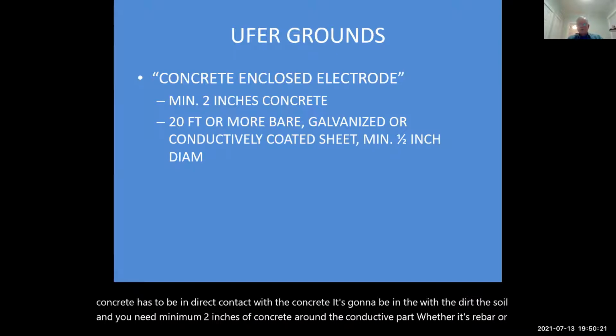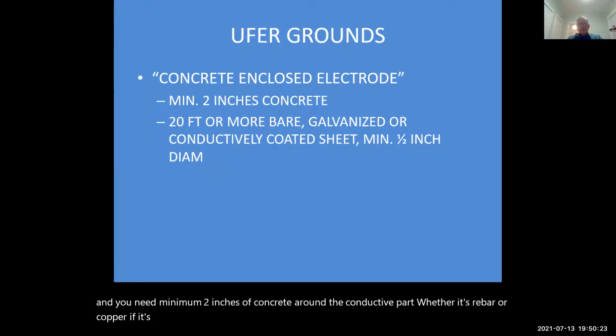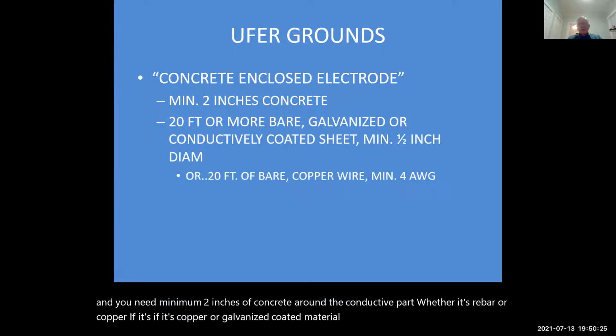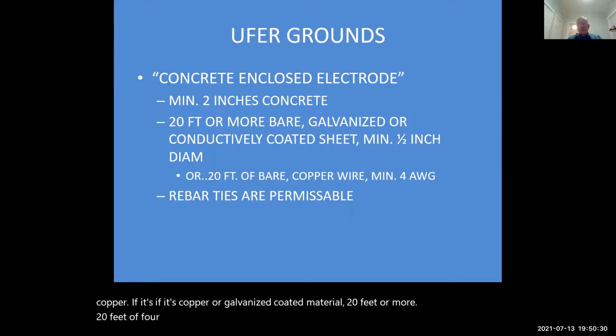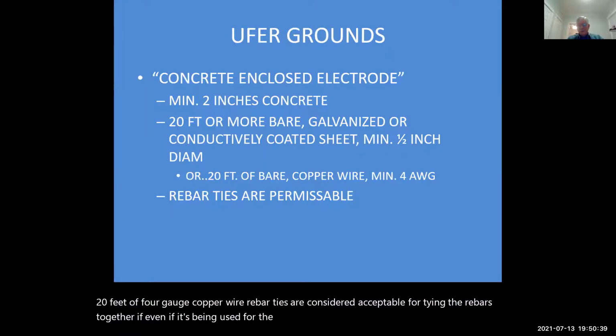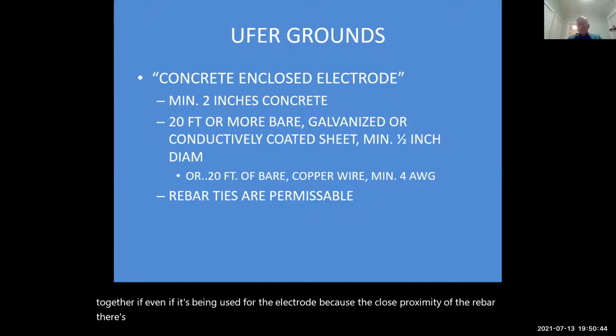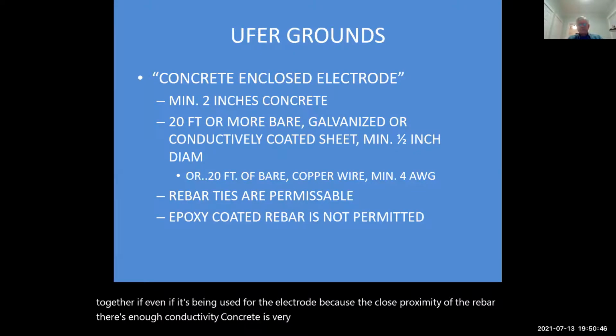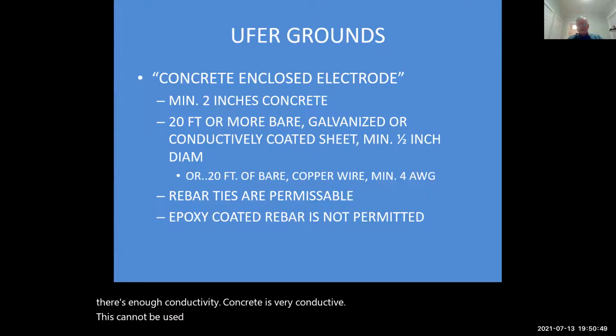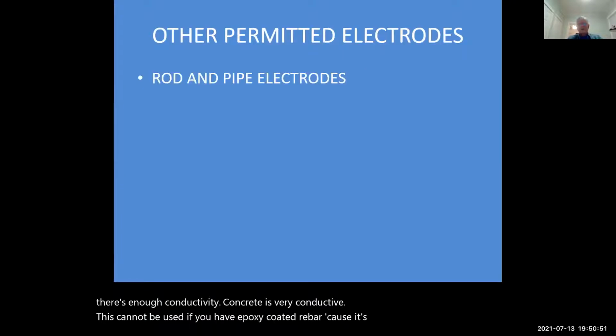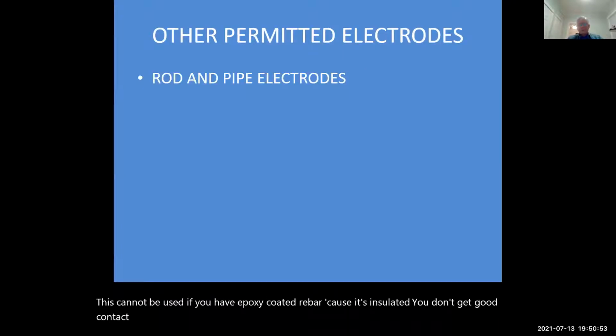If it's copper or galvanized coated material, 20 feet or more, 20 feet of 4-gauge copper wire. Rebar ties are considered acceptable for tying the rebars together, even if it's being used for the electrode, because of the close proximity of the rebar, there's enough conductivity. Concrete is very conductive. This cannot be used if you have epoxy coated rebar because it's insulated. You don't get good contact, and without wasting too much time.